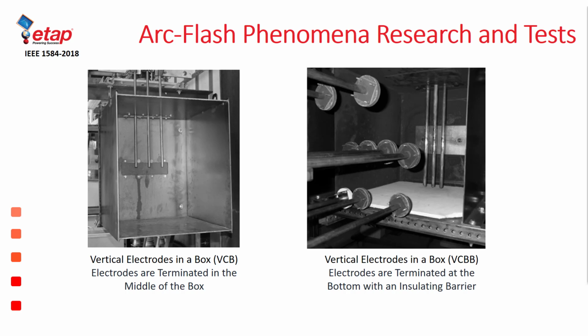The image on the left side of this slide represents the test setup at the core of the IEEE 1584-2002 model. This particular electrode configuration existed and is currently handled by the 2002 model. Note that the electrodes are open-tipped and are placed inside the enclosure at a certain depth from the open front end of the test enclosure or box.